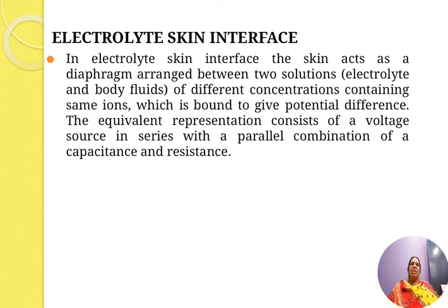So in the electrolyte-skin interface, the skin acts as a diaphragm arranged between two solutions of different concentrations containing the same ions, which is bound to give a potential difference. It consists of two solutions, the electrolyte and the body solution, with the skin acting as a diaphragm. The different concentration of ions is bound to give a potential difference.